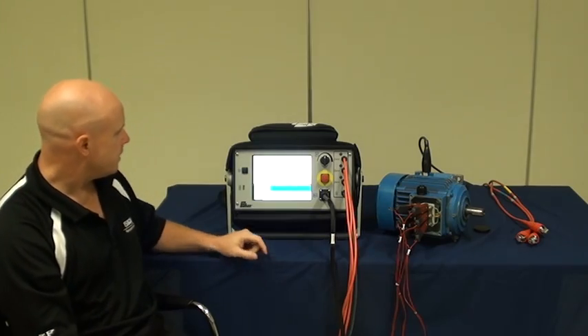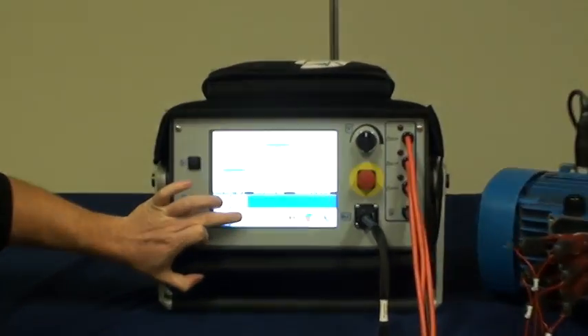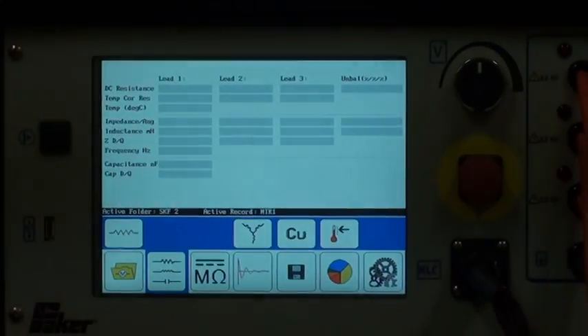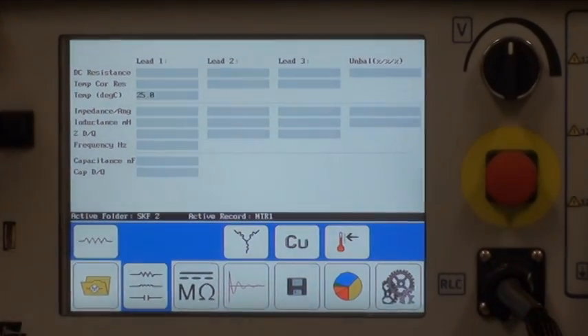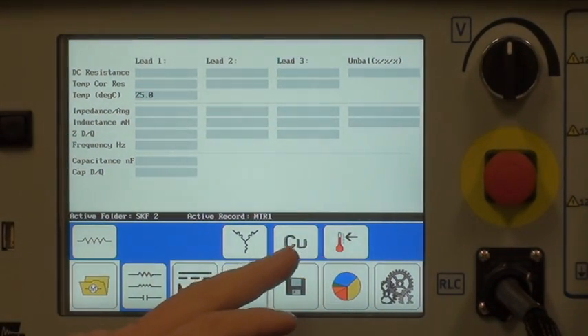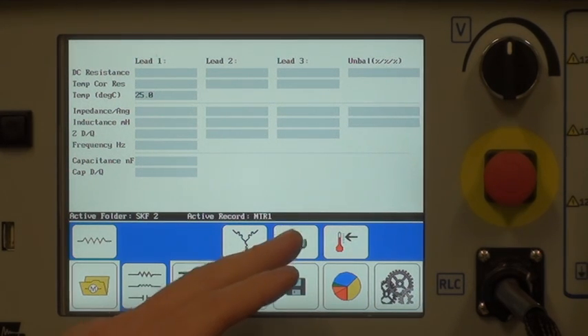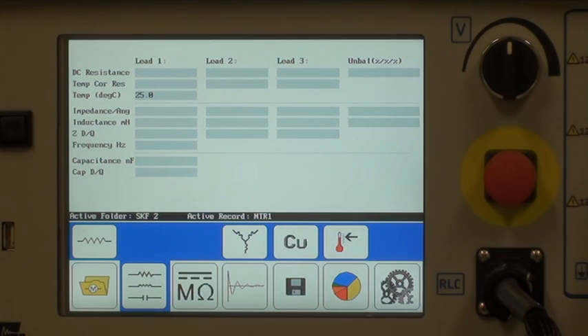Now what I'll do is touch the low-voltage test button, and it opens this screen. Here we can record the temperature, or if we're using aluminium wire instead of copper, we can change it there, and we can even put the connection in if we wish.